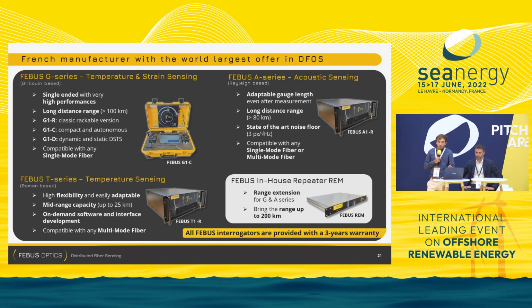So, to address all these types of events, to address this complete monitoring of cable, we need all the products that we manufacture with the largest distributed fiber optic sensing offer. The G series for temperature and strain, A series for acoustic, and T series only for temperature. The length of measurement is about 70, 80 kilometers, but this can be enhanced with some in-house repeater, and we can go to 200 kilometers.